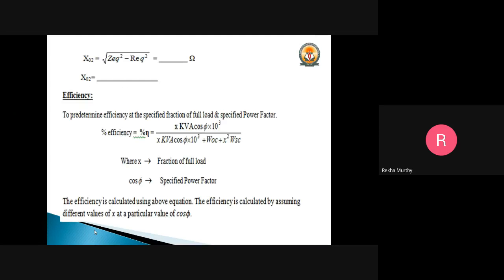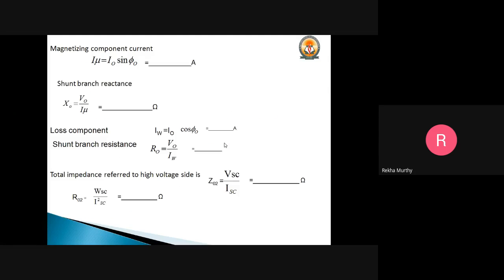The efficiency formula is: η = (X × kVA × cos φ × 10³) / (X × kVA × cos φ × 10³ + WOC + X² × WSC), where WOC is the open circuit wattmeter reading and WSC is the copper loss of each transformer. We also calculate the components of the no-load current: the magnetizing component Iμ = I0 × sin φ0, and the loss component IW = I0 × cos φ0.